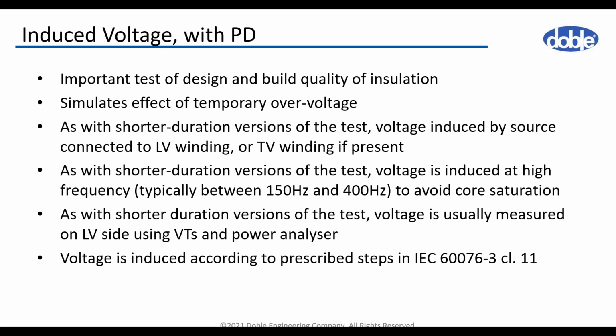The induced voltage test is the last dielectric test. It is the most important and probably the most stressful test for the dielectric system. It produces temporary overvoltage at a few different voltage levels, as described in IEC 60076 part 3, item 11. The voltage source for this test is usually a test generator or static converter at frequency higher than the rated one to avoid core saturation. Typically, test frequency between 150 and 400 Hz is used for that purpose.